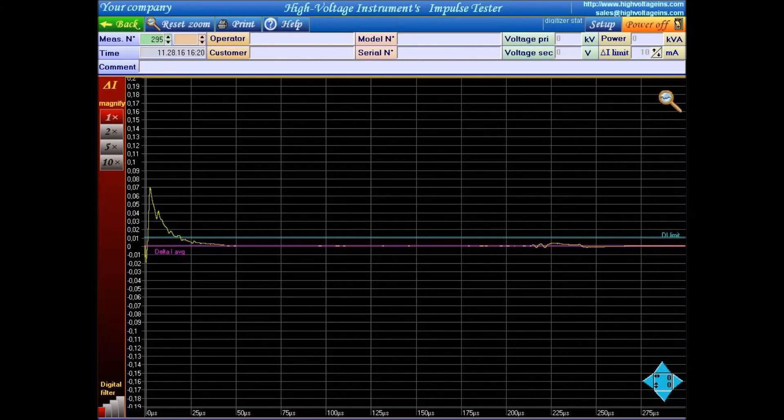The red line is a measured current difference integrated from 20 microseconds to 100 microseconds. It is less than 10 milliamp. The transformer will pass.